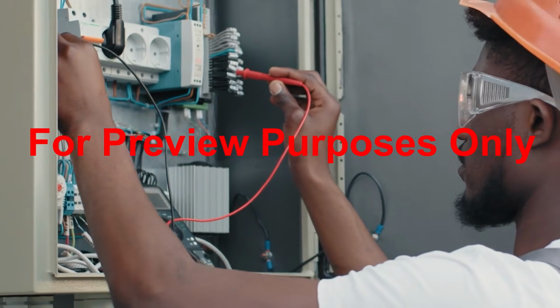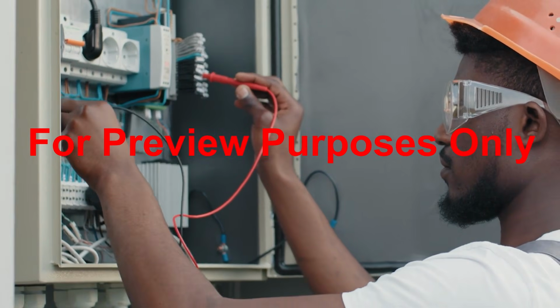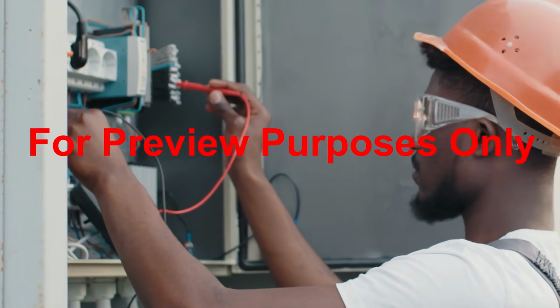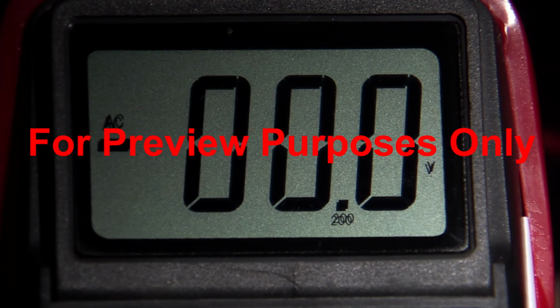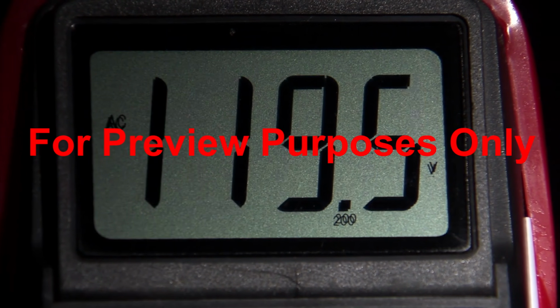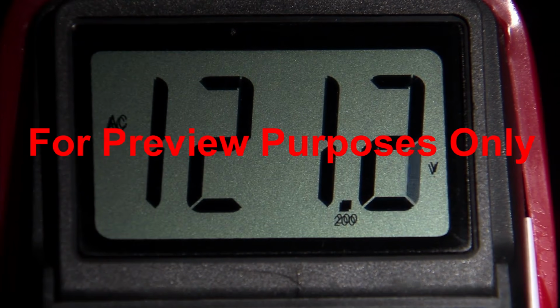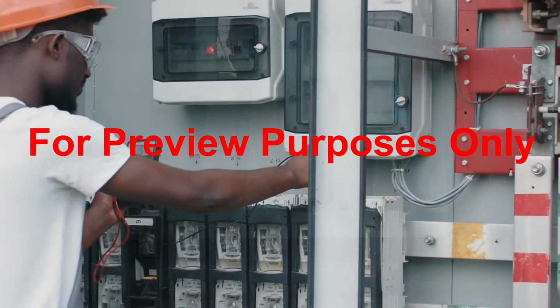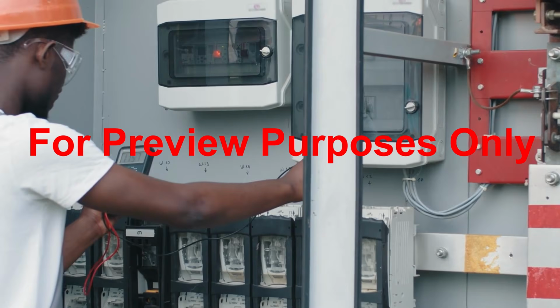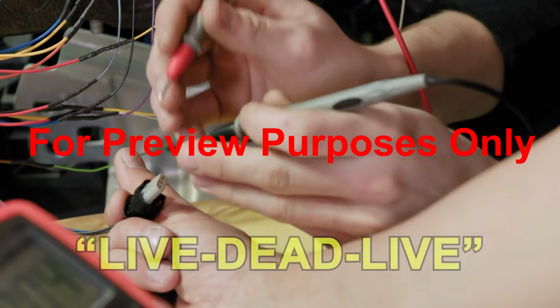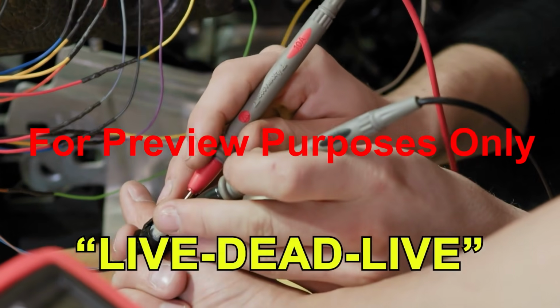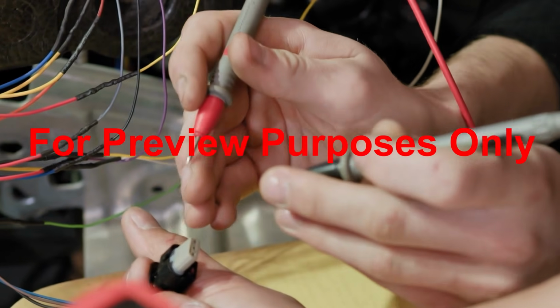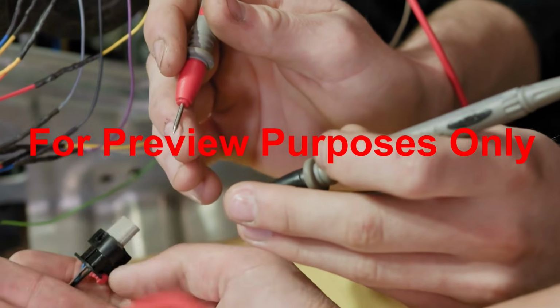When you are testing the equipment to verify that an ESWC has been established, remember to use a known source of voltage to ensure that the test instrument is working correctly, both before and after you use it on each circuit. This is called the live-dead-live test and will help to make sure that your results are accurate.